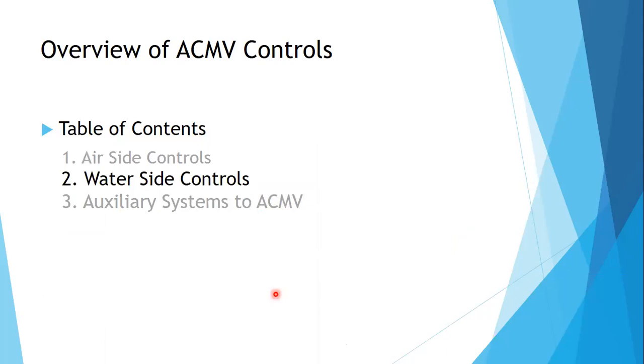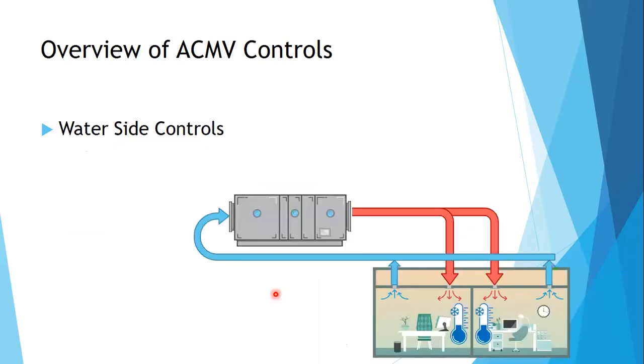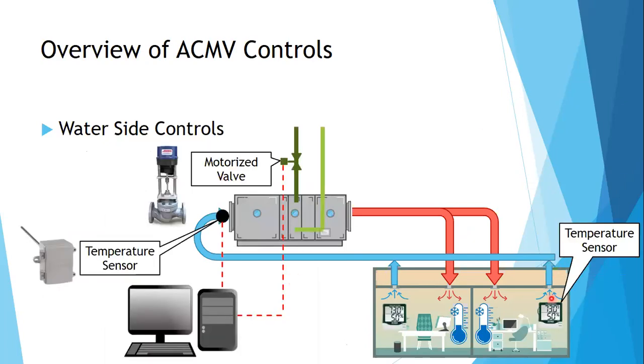Let's go with the water side controls. So here's another example. This equipment, we're cooling down one office and there's a temperature sensor. Let's say the temperature sensor says it's too cold, but we need the airflow here. The airflow is required. We cannot lower it down because of the fresh air requirements. If we lower down the quantity of air, your fresh air will also be less, which is not an ideal condition. So instead of lowering down the quantity of air, what we can do is to control the chilled water going in.